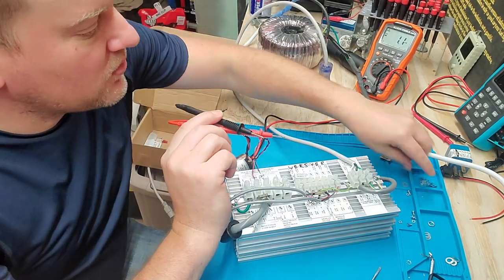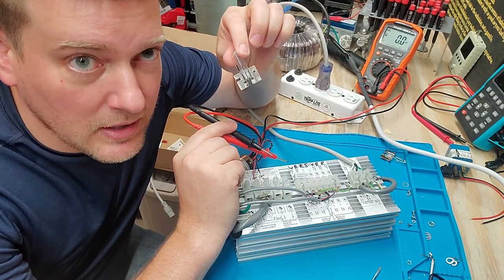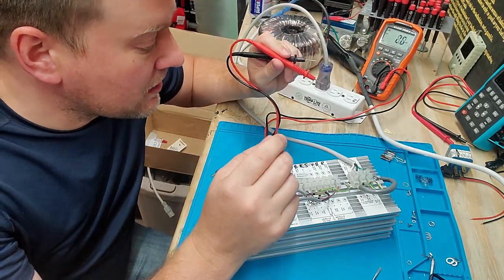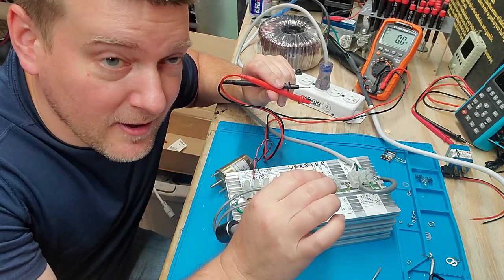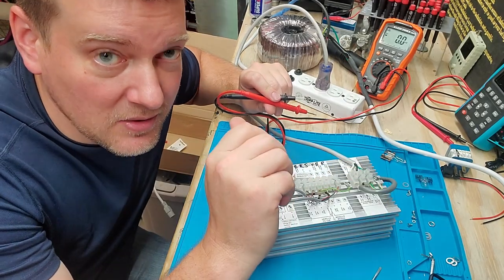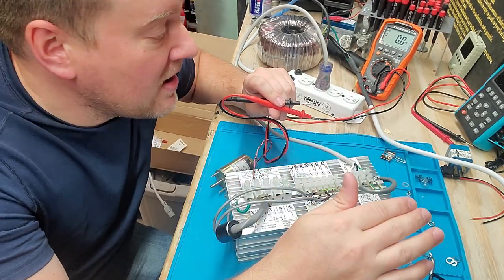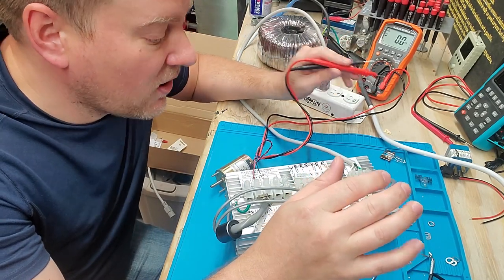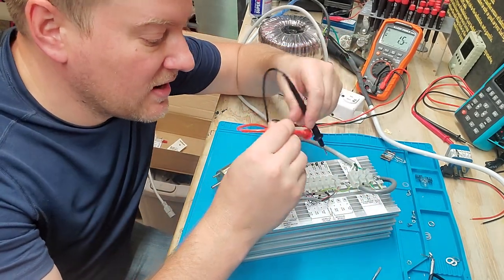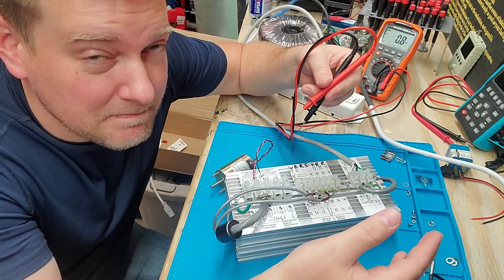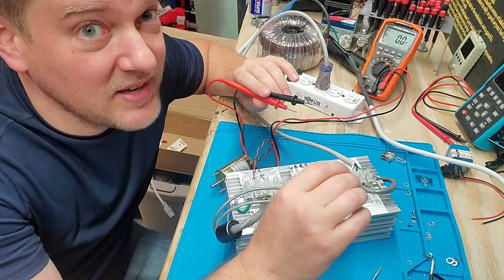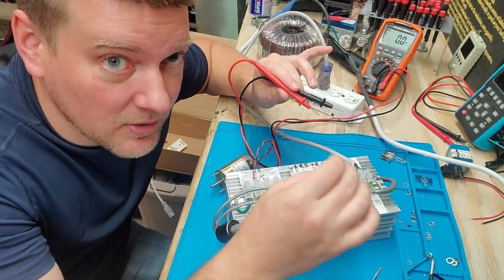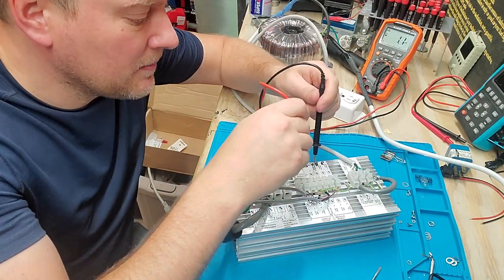I popped one of these fantastic little I think they're 20 or 30 dollar bulbs. Because what I did is, while this was in circuit, there was no way of killing the power to this in the room. I had to kill the main breaker to the room in order to do that. So what I could do is I put my meter on ohms and I came over here and I was measuring the potentiometer while it was still connected. And there's actually a bus that it plugs into so it's not the easiest thing to isolate to test independently.